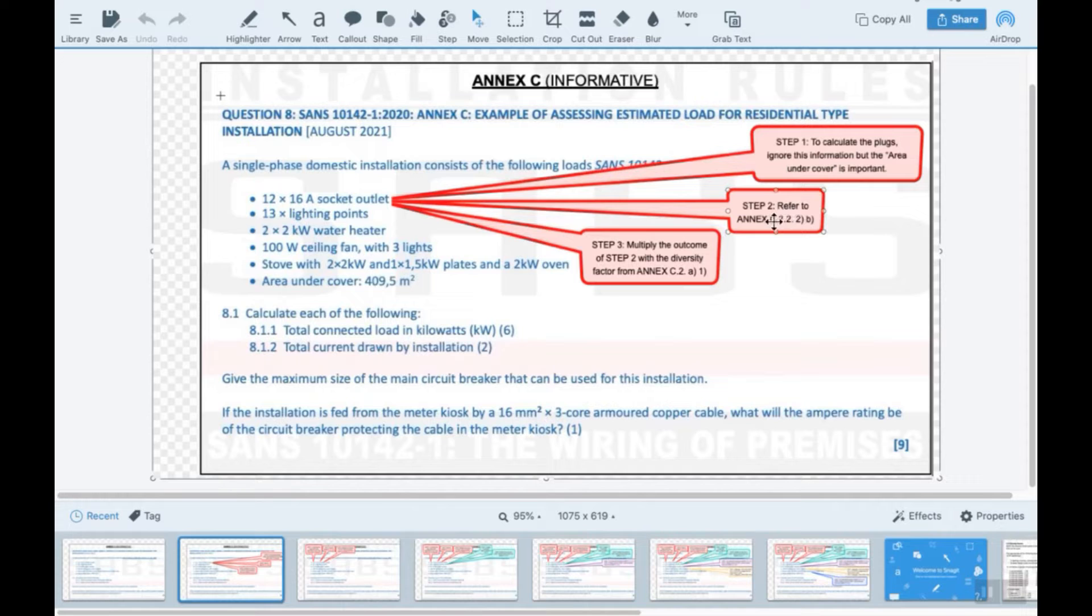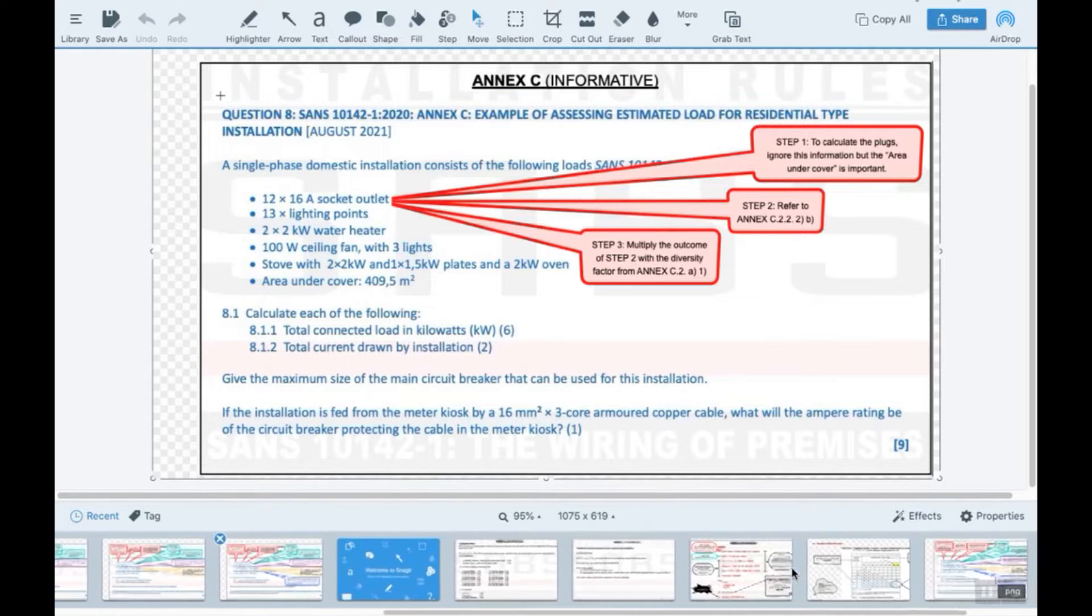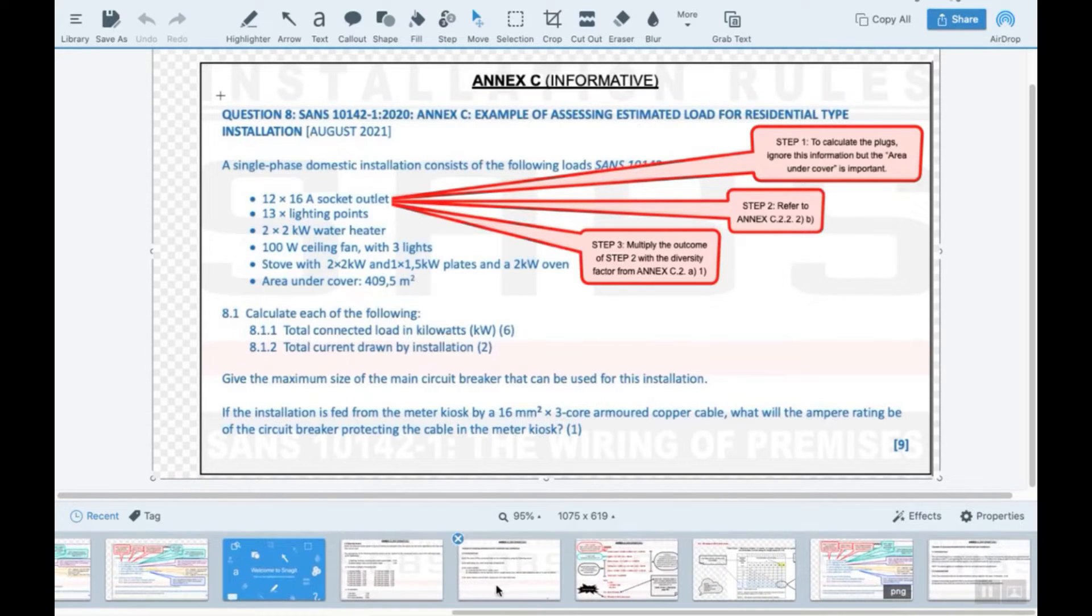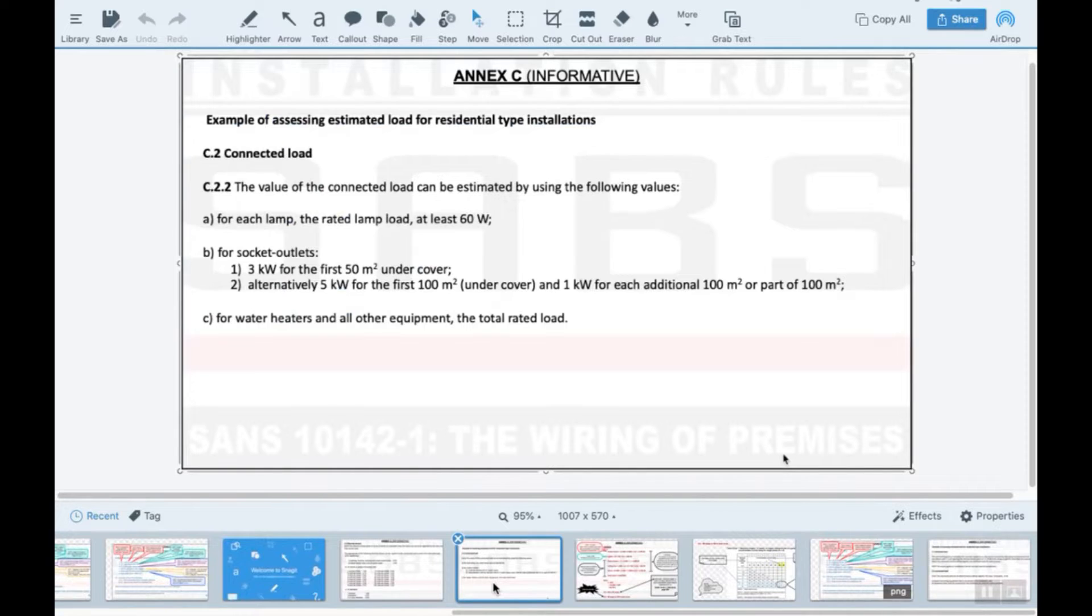So it says here step two, refer to Annex C 2.2B. So C 2.2B, and I need to look at the square meters. I will use this one because I don't have less than a hundred, so I will use this. There's three parts to this: part one is five kilowatt for the first hundred square meter under cover, then one kilowatt for each additional one hundred square meter, or a part thereof would be the third part.